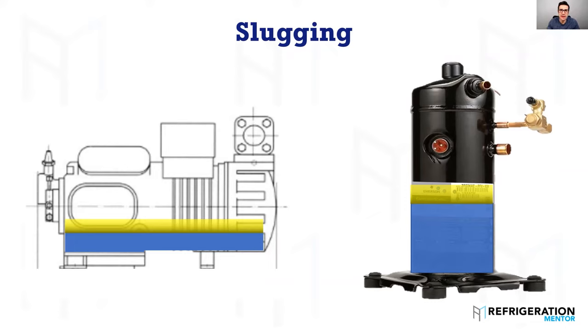Today I want to talk about slugging, the effects of slugging, and give you a better understanding of the different types of mechanical failure. When you say liquid caused an issue, you need to understand what that liquid is and be able to explain yourself, because slugging actually is two — maybe even three — separate mechanical issues. Flood back causes slugging, flooded start causes slugging, and too much oil or uncontrolled oil return causes slugging.